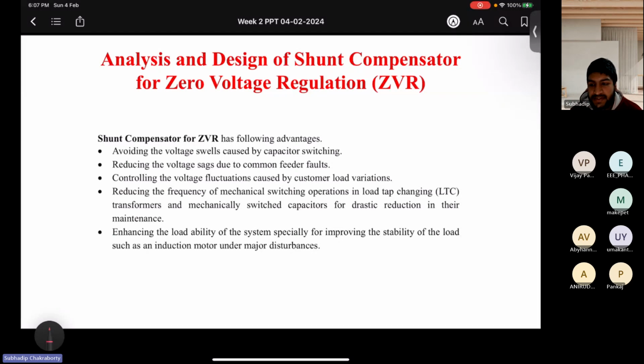Mostly at the distribution side, it is more of a problem rather than the power generator side, because the load current is changing quite abruptly. So when you have a bus at the distribution side, some voltage is there, the line has some impedance, and then you are feeding your loads, right? If this current at the distribution side is changing quite abruptly, the voltage across the loads is quite variable. From daytime to night time, even in our houses, the voltage that is coming is quite varying. So these may lead to some damage of our equipment. In the remote areas, it is quite common.